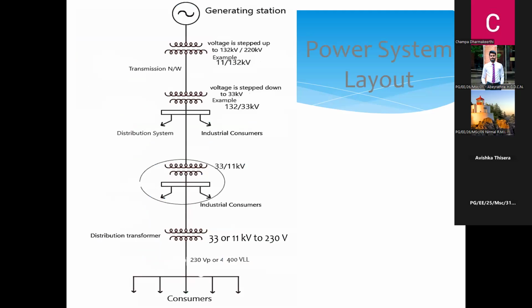So this is a typical power system layout, a traditional one, where we have a generating station. Thereafter, the step-up transformer. Normally, if we consider large scale hydro and thermal, generation happens in the kV range, like 11 or 13, less than 20 kV is a typical value. Then we step up those voltages to transmission level voltages. In our country, it's 132 kV and 220 kV. Then the power is transmitted. We increase the generated voltages to transmission level voltages in order to reduce power losses along the line and voltage drop.